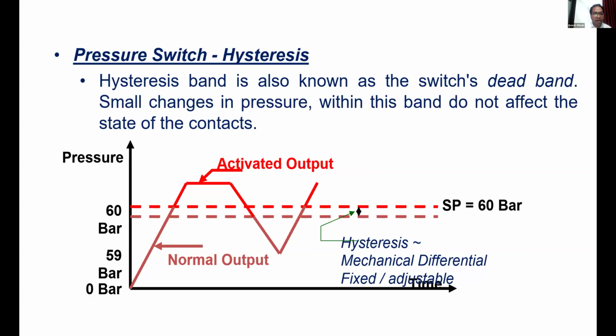That's the reason I have given some hysteresis band. It means we need to set the band manually. For example, if the pressure is 60 bar, I will set the hysteresis band from 59.5 to 60.5. Till then, it will not change the output. So it is necessary to set the hysteresis band in every sensor to avoid the chattering of that particular sensor. The hysteresis band is also known as the switch band or dead band, and it will save the sensor from chattering.